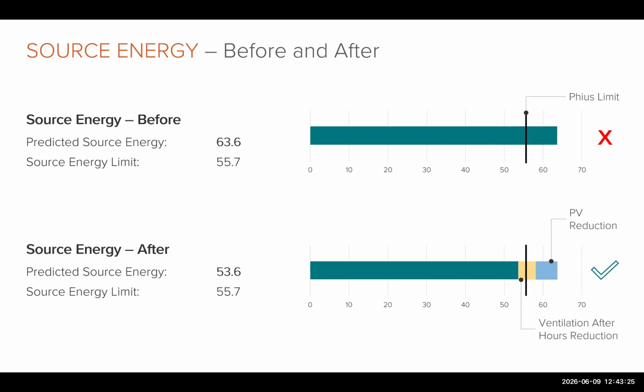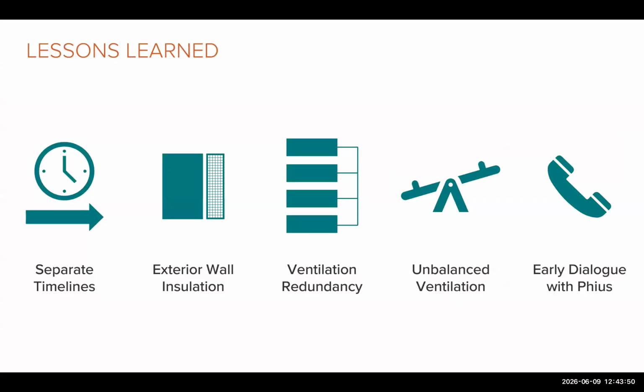It was only after reducing the ventilation after hours from the ERVs, bringing us down the amount shown in yellow, that we finally squeaked under that limit of 55.7 kBTUs per square foot per year. With that, I will turn it back to Lauren to summarize things and talk about cost savings. Thanks, Kristen. I'm going to close out with both lessons learned and with some potential energy cost savings.